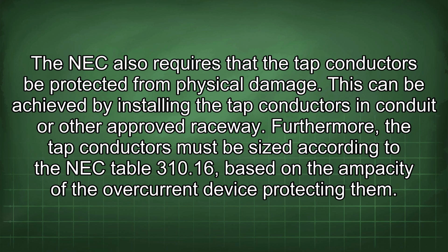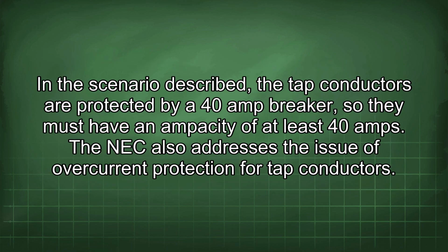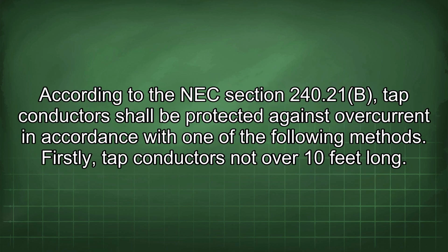Furthermore, the tap conductors must be sized according to the NEC Table 310.16, based on the ampacity of the overcurrent device protecting them. In the scenario described, the tap conductors are protected by a 40 amp breaker, so they must have an ampacity of at least 40 amps. The NEC also addresses the issue of overcurrent protection for tap conductors.